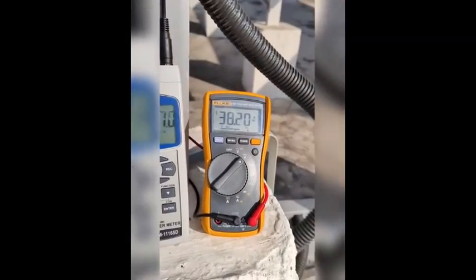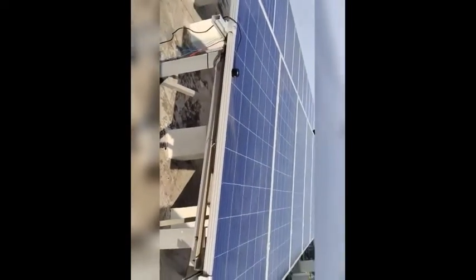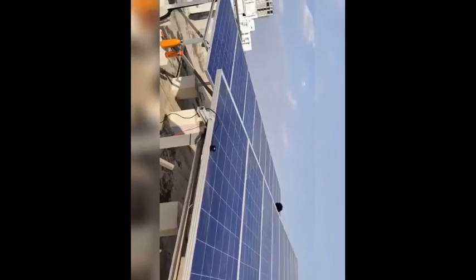The test module was connected to one of the panels and the test was executed at an irradiance of 470 Watt per meter square and at a temperature of 27.8 degrees Celsius. The panel, which is operating in a healthy mode, delivered a voltage of 38 volts.